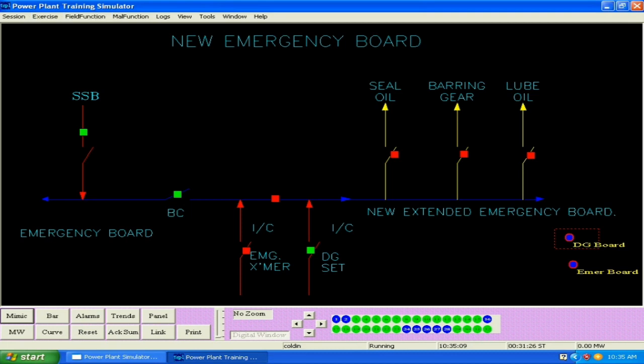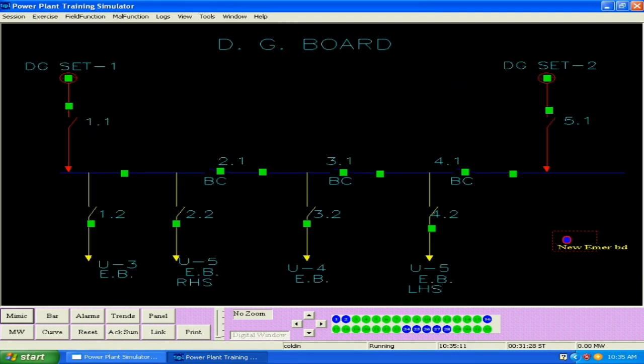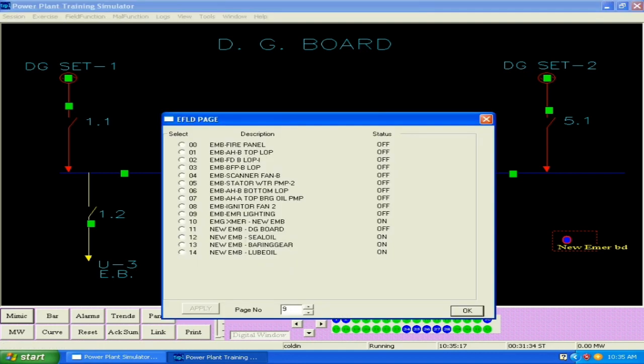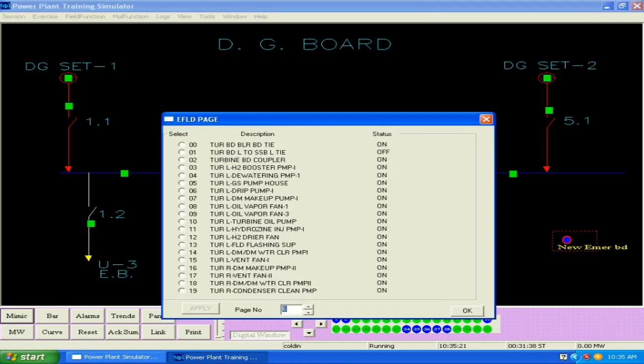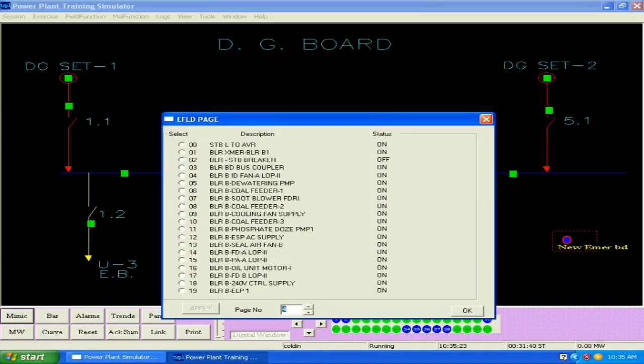You can see that all the indications are red. Now we can go to the DG board. We can charge the DG board. DG sets will be required in case of emergency when there is total AC failure. So for that purpose we have to make the DG board also ready. Check up that the DG sets are ready. So observe the DG board mimic.